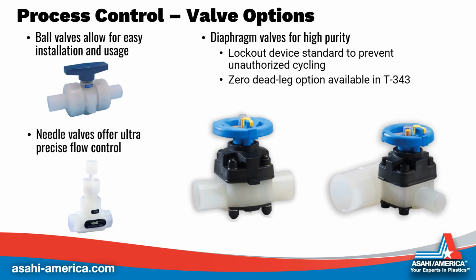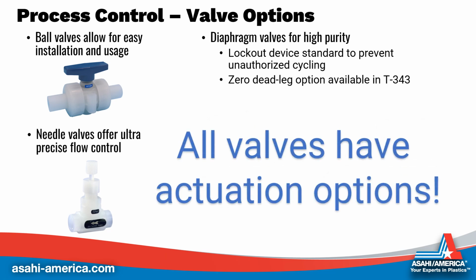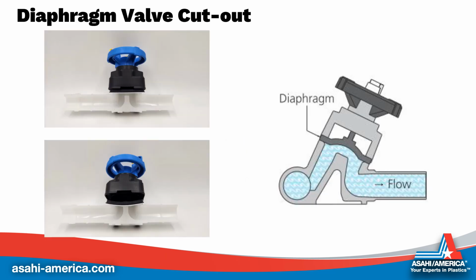PolyPure is available in multiple valve options for your specific system needs. Ball valves allow for easy installation and usage. Needle valves offer ultra-precise flow control. Diaphragm valves are popular within high-purity systems. They come standard with lockout devices to prevent unauthorized cycling, and on the T343, a zero deadleg option is available. Both of these valves are offered as manual valves, but can be used with actuation just like any of the other valves we offer. Sealing gaskets for all these valves are offered in multiple materials. Presented on the screen is a bisection of our T342 diaphragm valve, alongside a diagram of our zero deadleg T343 diaphragm valve. These valves are designed to limit stagnant water buildup when the valve is closed.